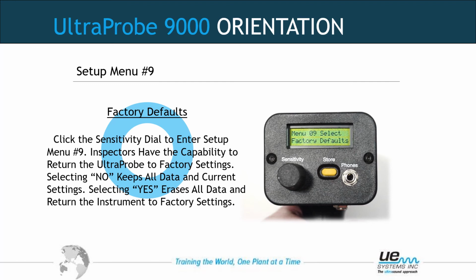On a side note, when you load a fresh route to the unit, it will clear the memory of the old readings and put the new route onto the unit. So there's no need to clear the unit. If you want an empty memory to go scan whatever it may be, you can connect the 9000 to the DMS software by cable, and an option to clear the memory is there in the DMS software as well.